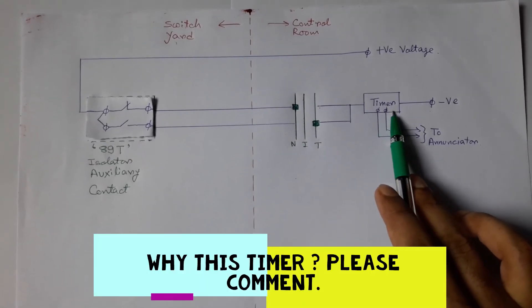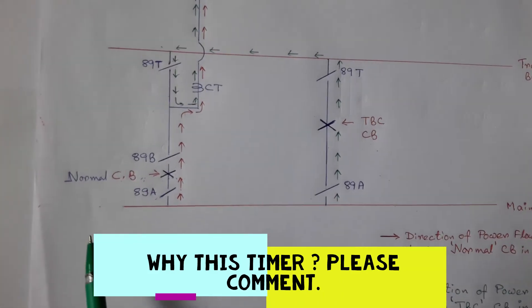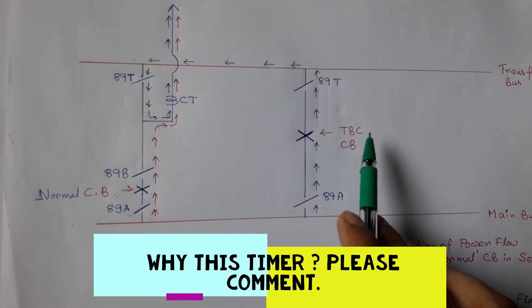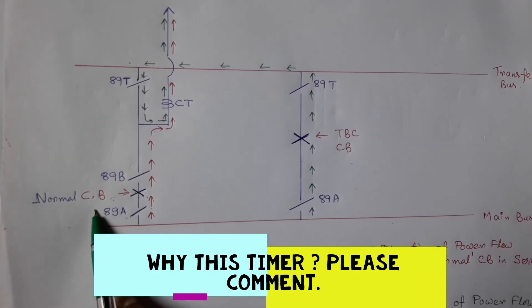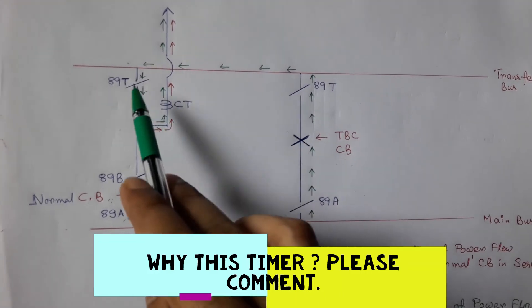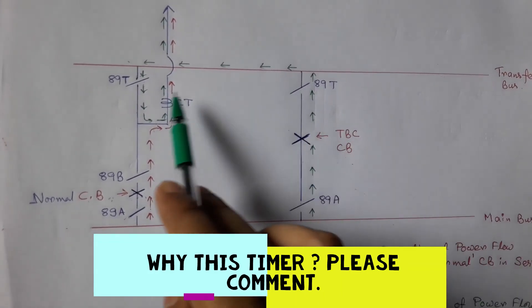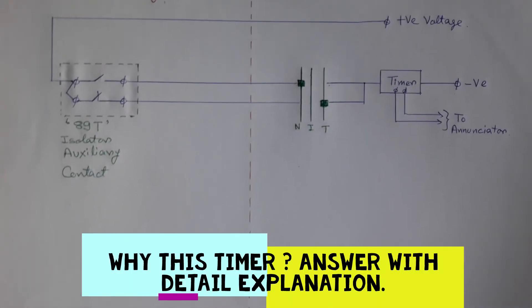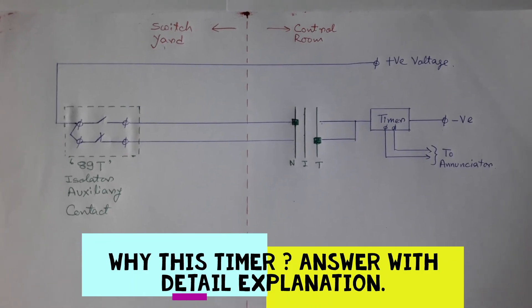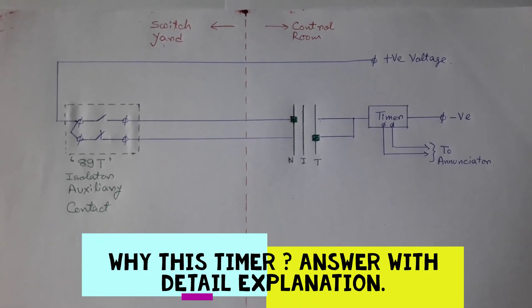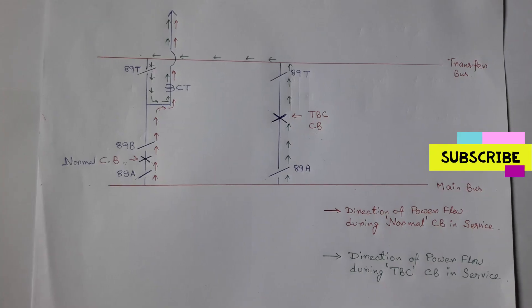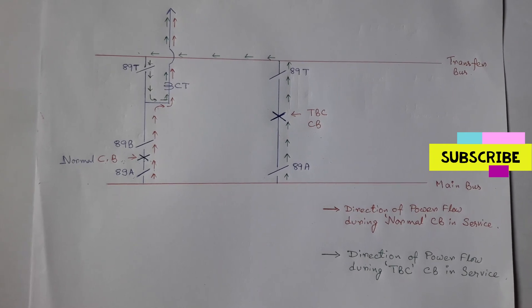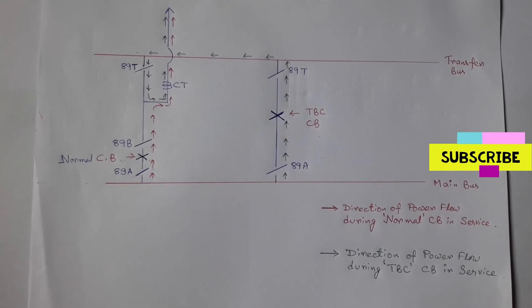But why do we use this timer? This is because during the load diversion process from normal CB to TBC-CB, or from TBC-CB to normal circuit breaker, there may be a situation where all five isolators are closed at the same time. During that condition, this scheme may provide a wrong indication, and to avoid that wrong indication, this timer is used. Hope you understand this topic. For more videos like this, stay tuned by subscribing to this channel and don't forget the bell icon.